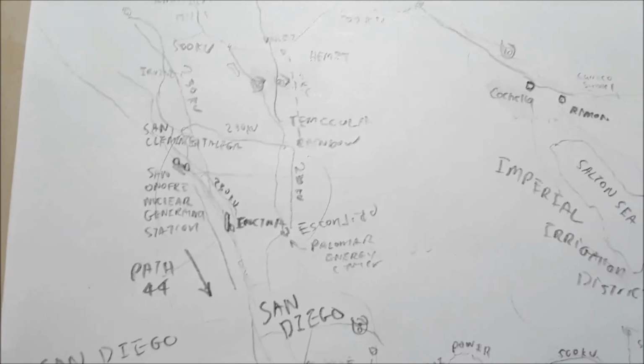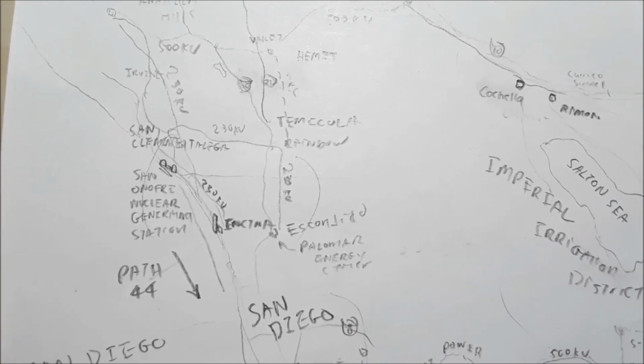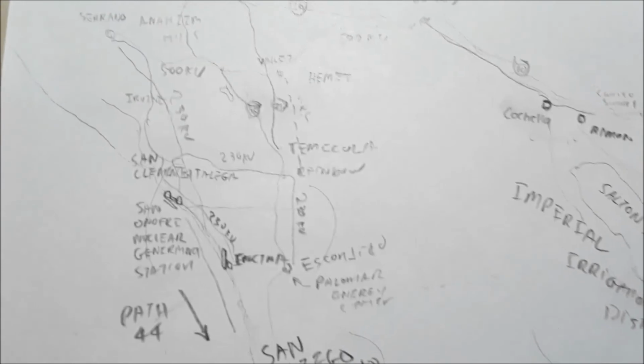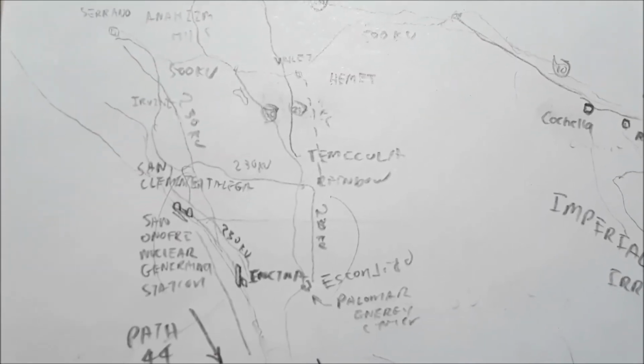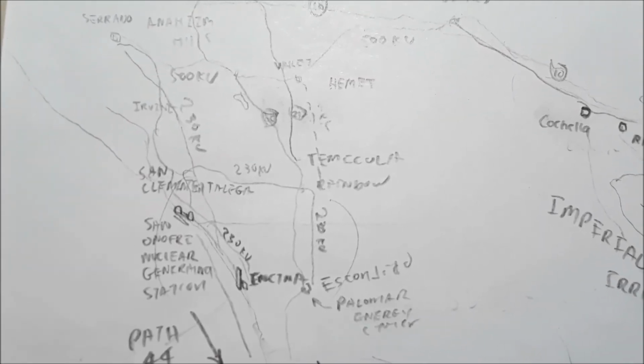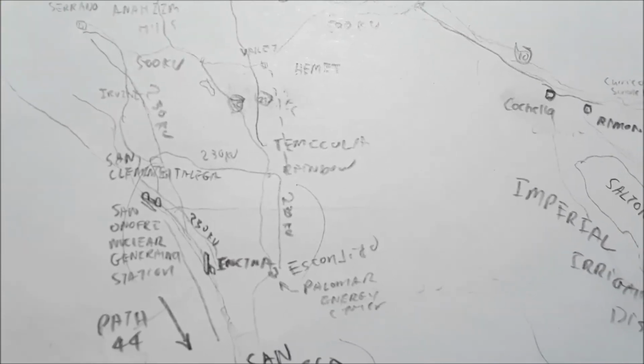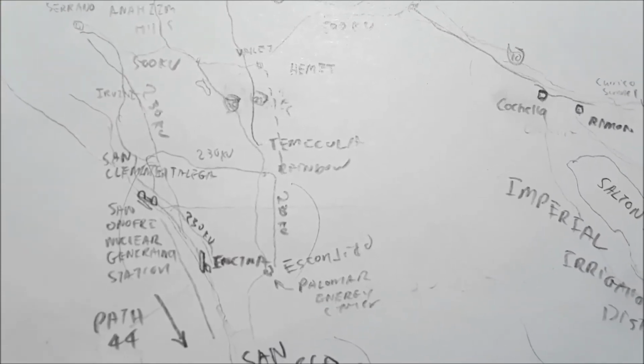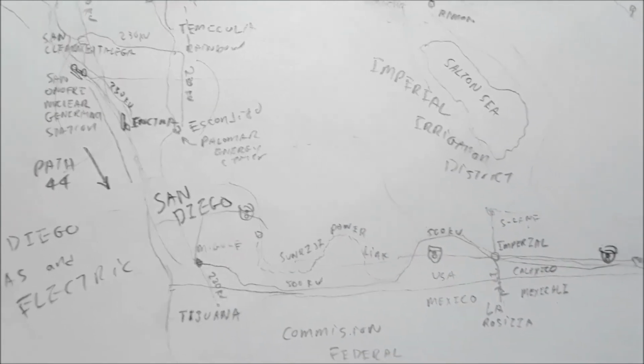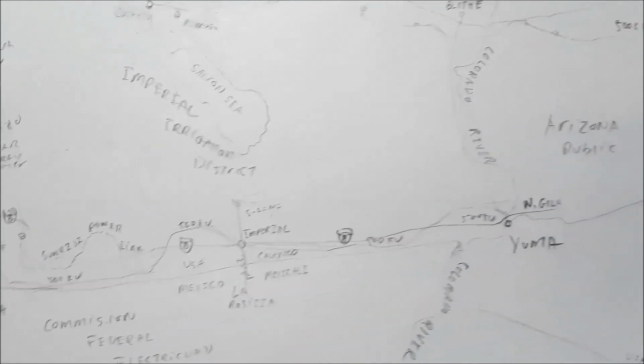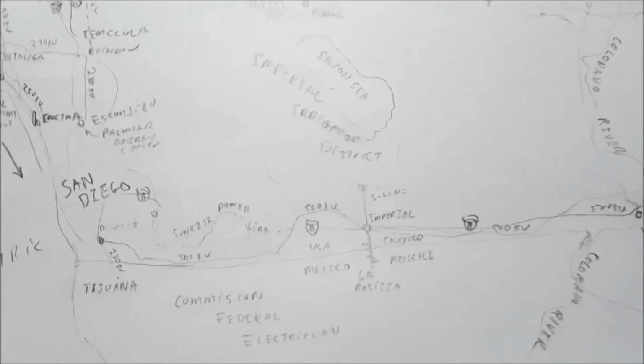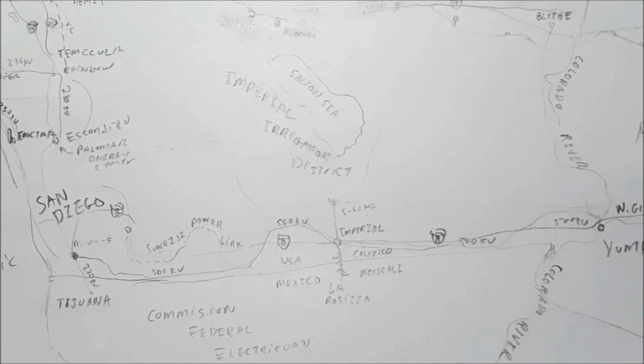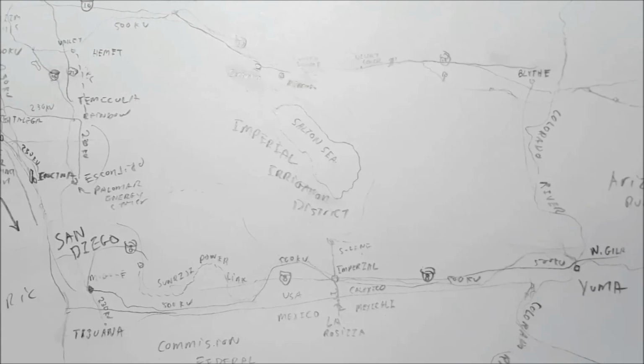Now, this draw was very high, almost a 170% overload, and a safety system called the SONGS Separation Scheme activated and disconnected the transmission lines going into San Diego. San Diego, Baja California, and Yuma, Arizona are now completely separated from the rest of the Western Interconnection grid.